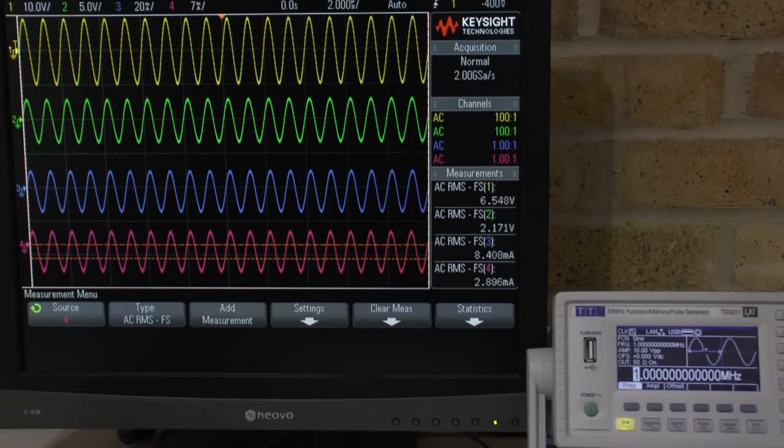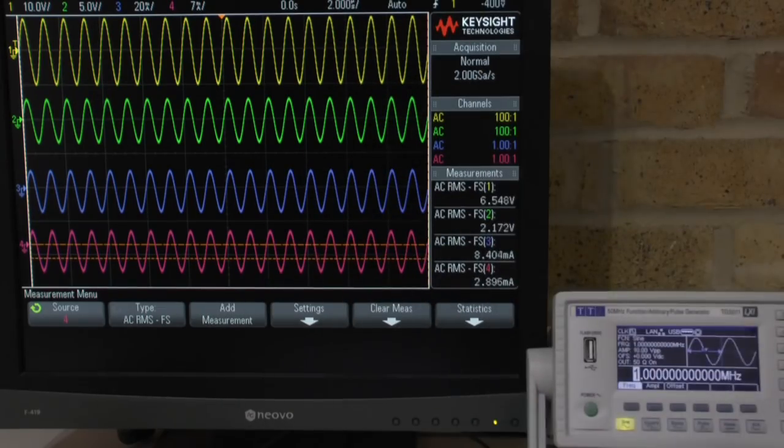Even if the ratio is not 1 to 1, we have an isolation transformer here which is behaving as expected. That means at lower frequency there is no deviation from the signal frequency. It will behave all the same. So we have it all aligned. They are all in the same phase to each other and that is what you would expect from an isolation transformer.